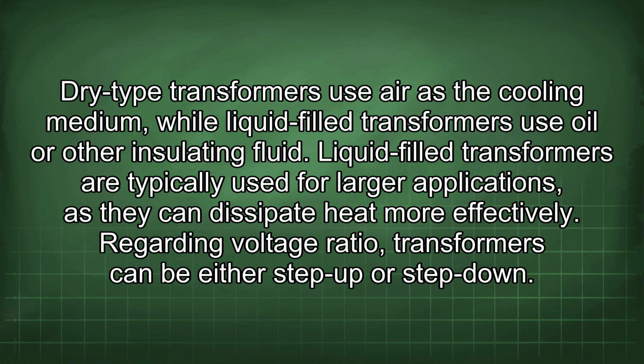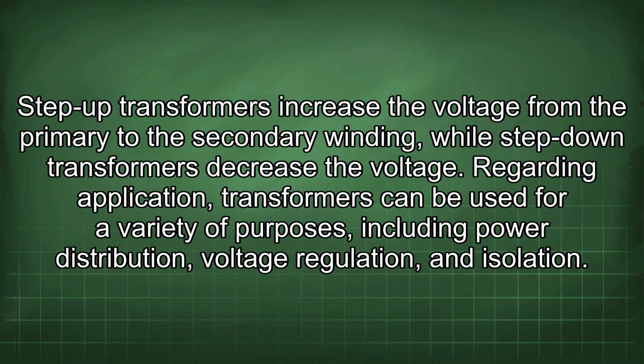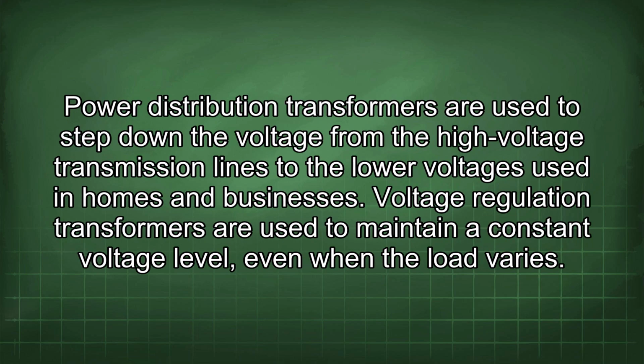Regarding voltage ratio, transformers can be either step-up or step-down. Step-up transformers increase the voltage from the primary to the secondary winding, while step-down transformers decrease the voltage. Regarding application, transformers can be used for a variety of purposes, including power distribution, voltage regulation, and isolation. Power distribution transformers are used to step down the voltage from the high voltage transmission lines to the low voltages used in homes and businesses.